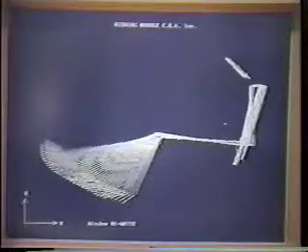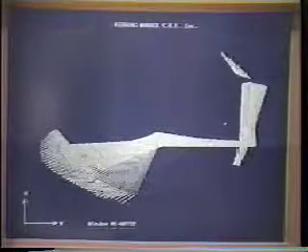Okay, we'll note that we have 90 pounds on the calibration, and we will further note that it is 90 pounds throughout the entire range of the motion of the bar, so that is a very accurate calibration. The ultimate internal validation and calibration procedure is the ability to accurately compare the results obtained by the arm-leg machine on the one hand and the digitizer on the other, while performing a velocity diagnostic procedure with the arm-leg machine.